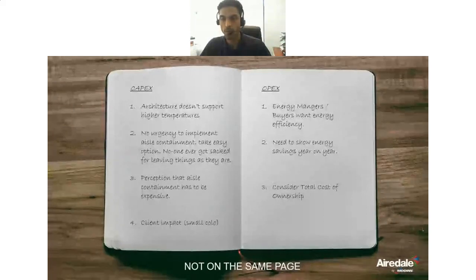While people from the operational side, the energy managers or sustainability heads, might be demanding more efficiency, savings and lower total cost of ownership, on the other side, when trying to reduce capex, the IT manager's reasons might be that the architecture is a legacy data center that doesn't support high temperature, or there's no urgency, or no containment solution was specified, so it's left as is, or there's a perception that a containment solution is very expensive, or it's simply a client decision.